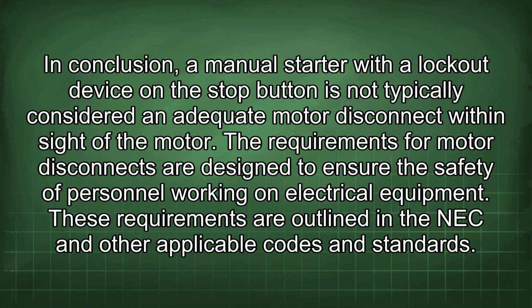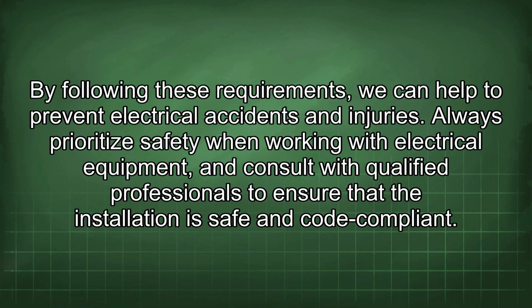In conclusion, a manual starter with a lockout device on the stop button is not typically considered an adequate motor disconnect within sight of the motor. The requirements for motor disconnects are designed to ensure the safety of personnel working on electrical equipment. These requirements are outlined in the NEC and other applicable codes and standards. By following these requirements, we can help to prevent electrical accidents and injuries. Always prioritize safety when working with electrical equipment, and consult with qualified professionals to ensure that the installation is safe and code compliant.